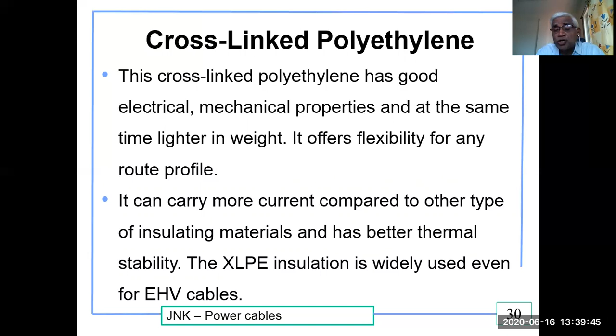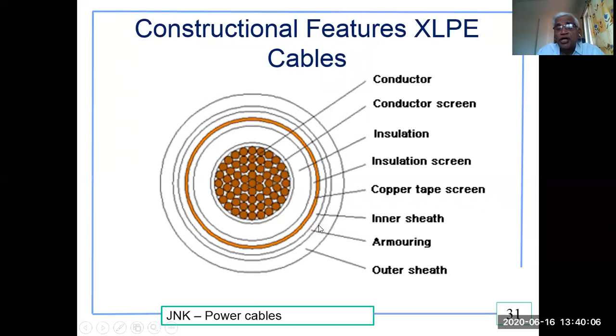Now, constructional features of XLPE cable. You can notice that you have a conductor here, and the conductor screen is the second one, and then the insulation material, and this is the insulation screen. Copper tape is there after that, and the inner sheath and armoring, and the outer sheath come after this. Now, XLPE insulation cable is for HV and EHV.